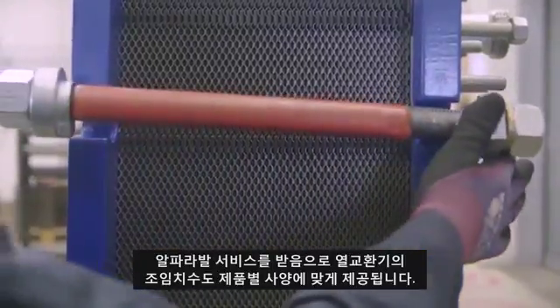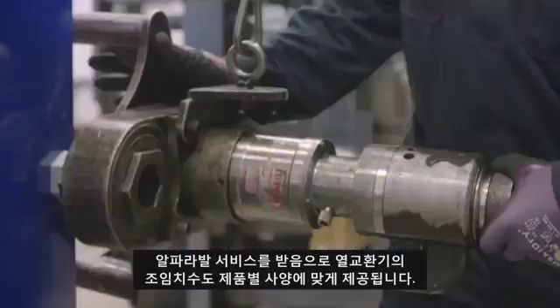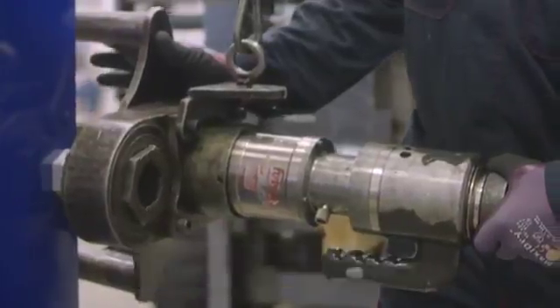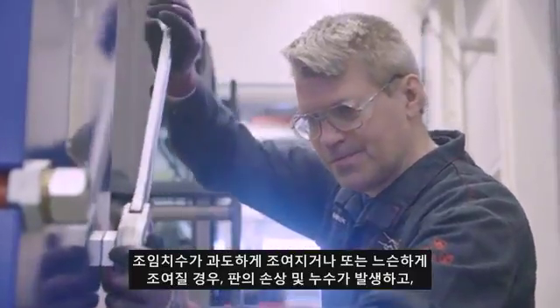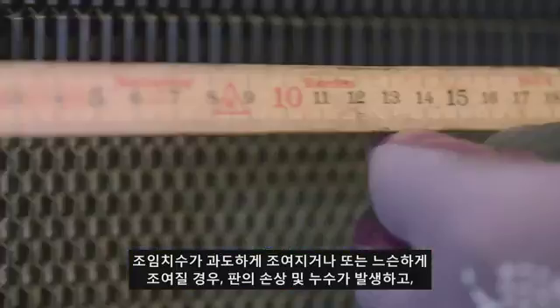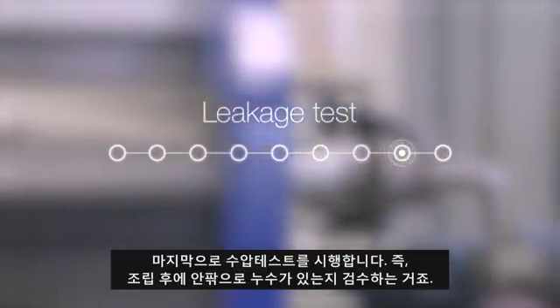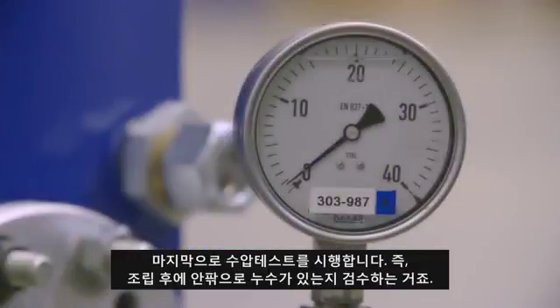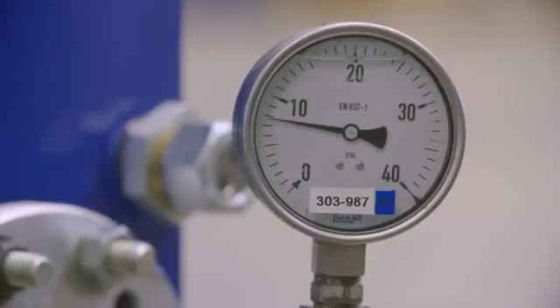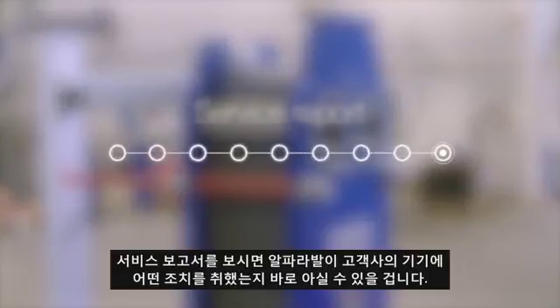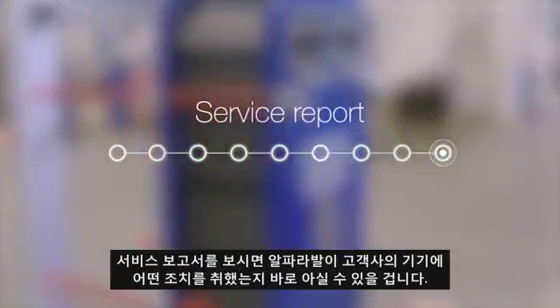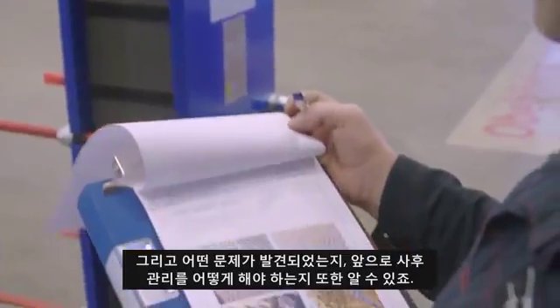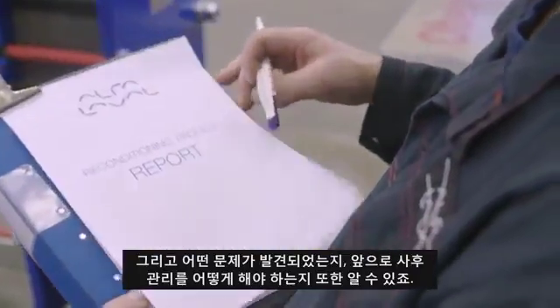By servicing the frame with us, you're also ensured to get the unit tightened to the right specification. Not over-tightened, not under-tightened, but to the right specification. And that avoids damaging the plates. At the end, we also do a hydrostatic test, and that is to detect any internal or external leakages after assembly. In our service reports, you'll be able to see exactly what we've done to the unit, the problems we've identified, and also advice on future maintenance needs.